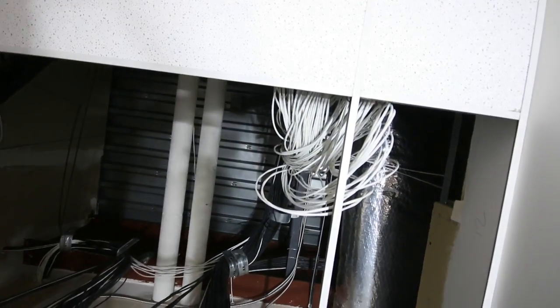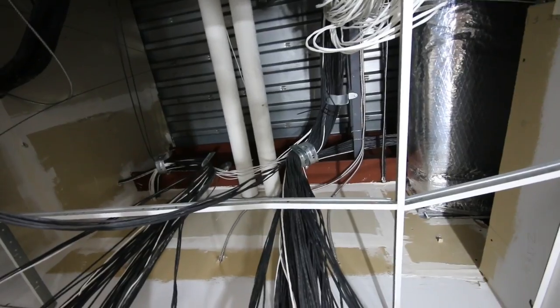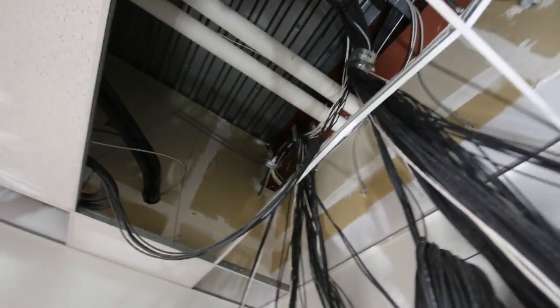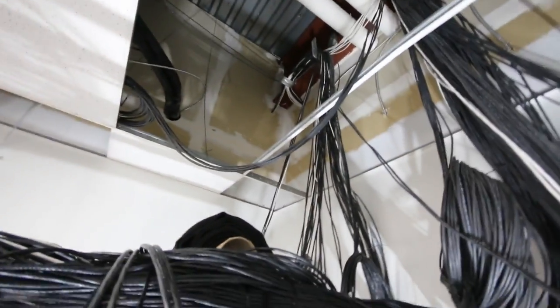It's still bundled up there because some of it's got to come back down, but you can see how we have the hooks in there. I can't really get up there to show you where we went over the HVAC and everything else, but you can see how it came around — we went over it at a beam level, so it wasn't even a factor. What we did is we came around with these 400-pound rated J-hooks and mounted them to 500-pound rated beam clamps. That's only because that's all you can really buy to hold that much wire up. That will support all of that wire, and we doubled them up at the ends where the waterfall comes down, so if one comes loose it's not going to knock your ceiling down. It's future precautions and basically keeping it up to code — we want to make sure it's extra solid in case they ever add more.